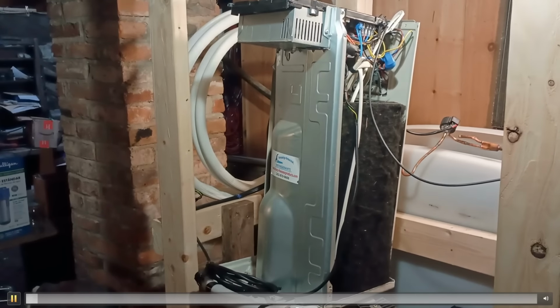Okay, so let's talk about sizing the trenches. In general, the rule of thumb is you need 600 feet of buried pipe per 12,000 BTU system. So I have an 18,000 BTU system, so I need 900 feet of piping, and I oversized. I really did more. I was targeting like 1,800 feet of piping. It's probably more in the 16 to 1,700 foot range.